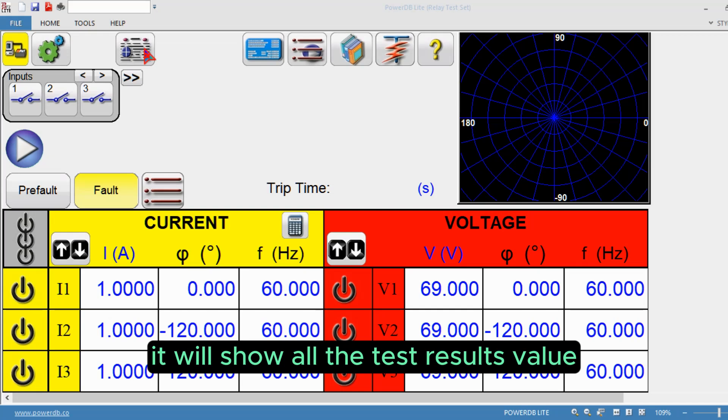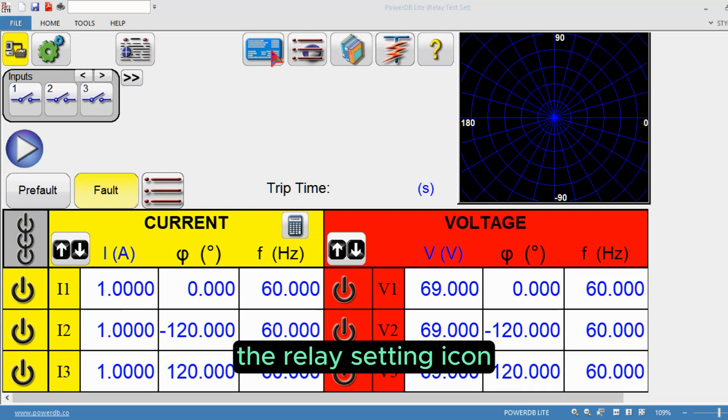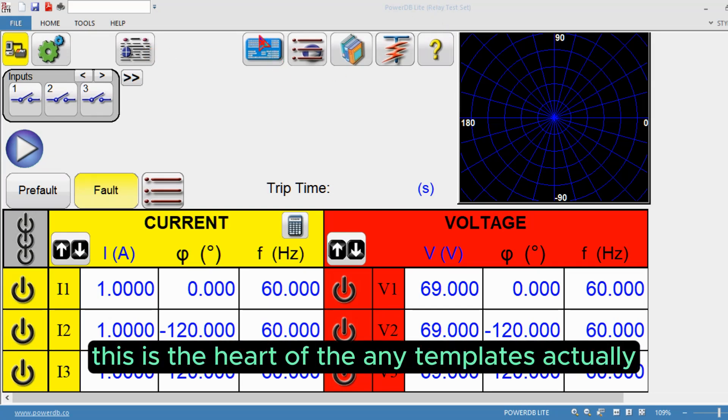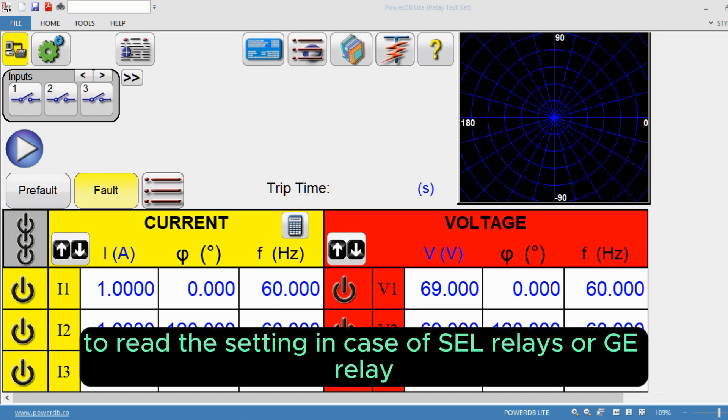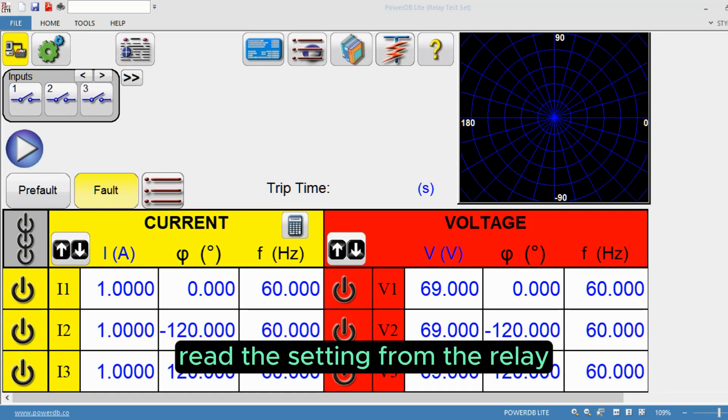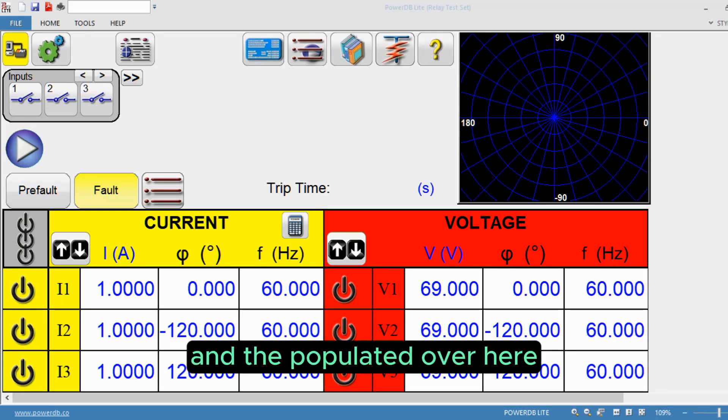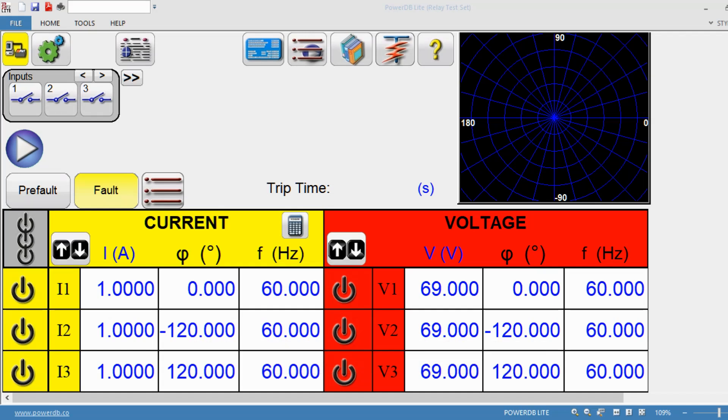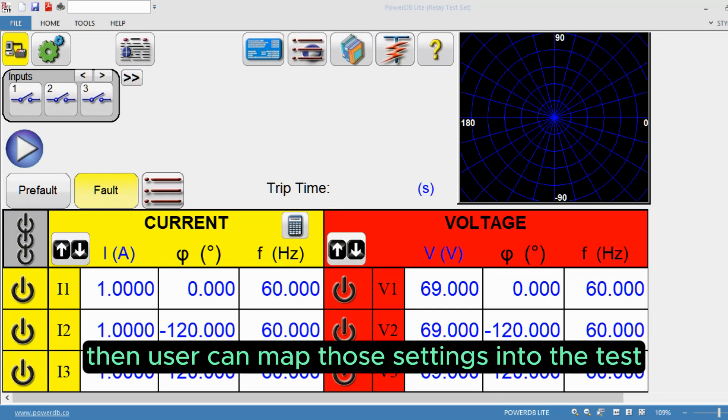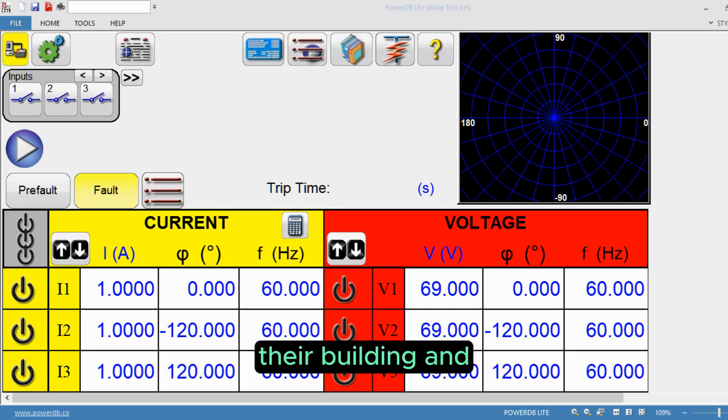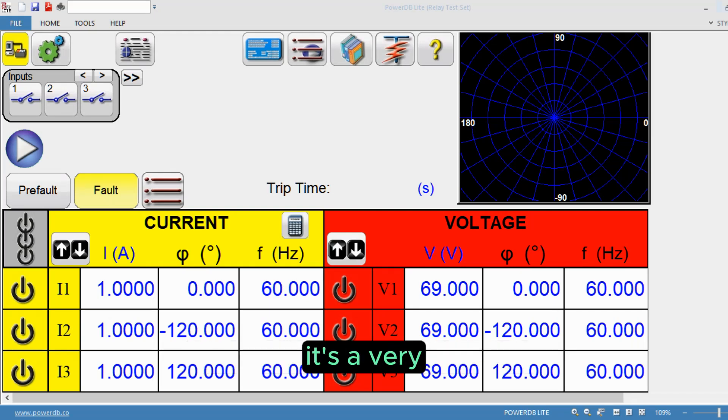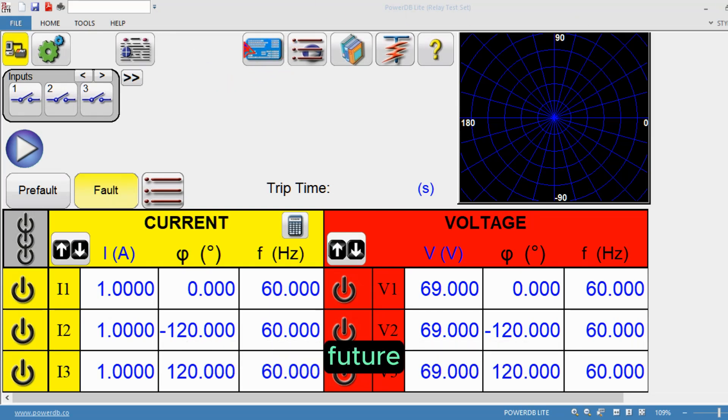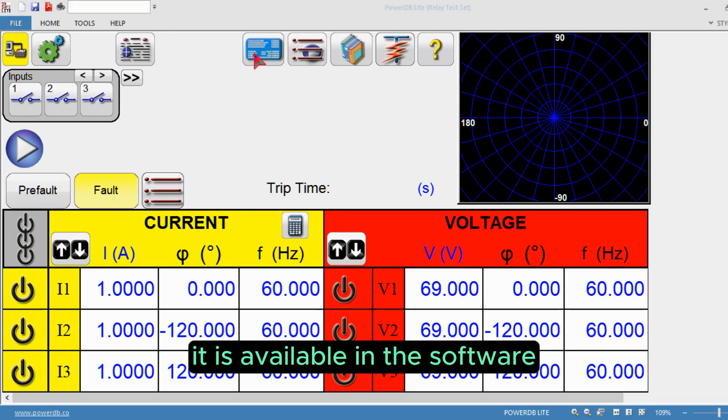The relay setting icon is the heart of any template. This icon helps users read the settings in case of SEL relays or GE relays, read the setting from the relay and populate it. Then users can map those settings into the test they're building and create the templates. It's a very important feature available in the software.